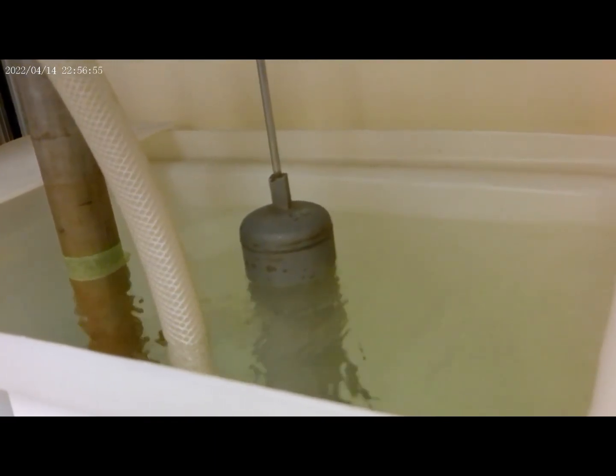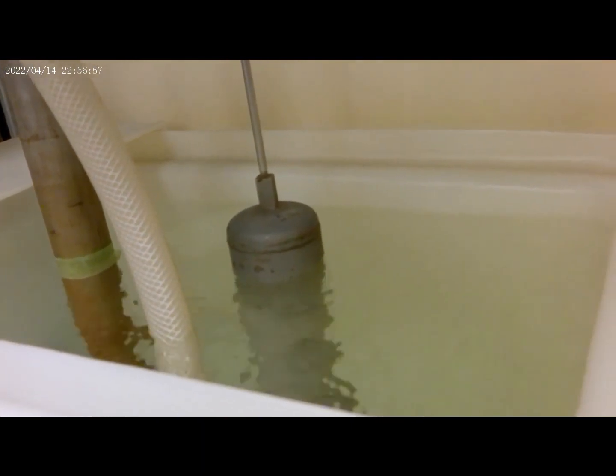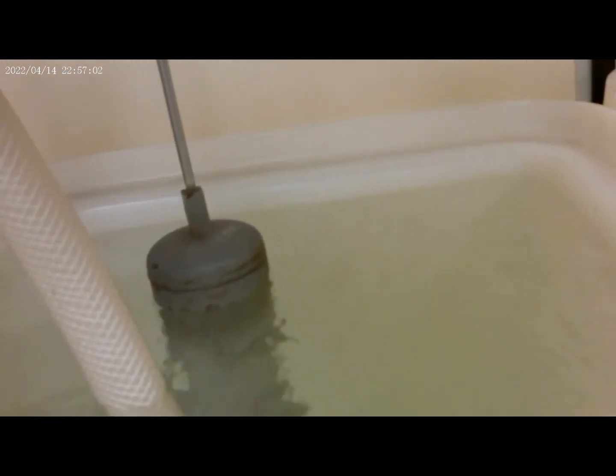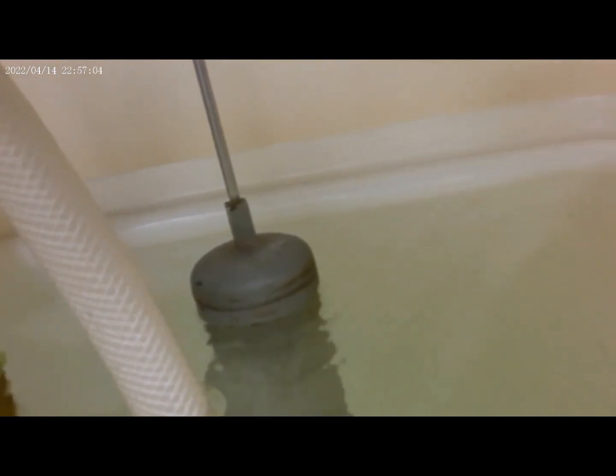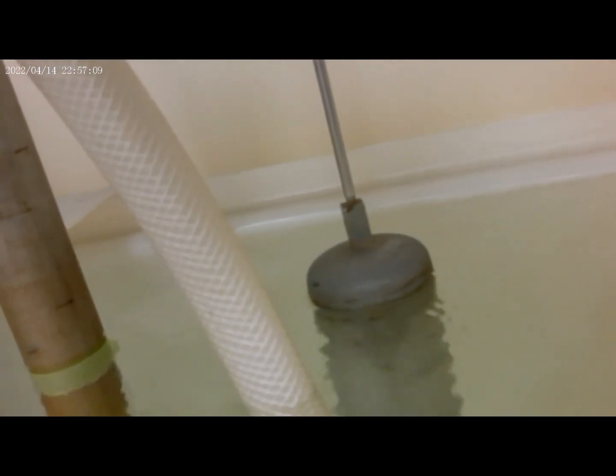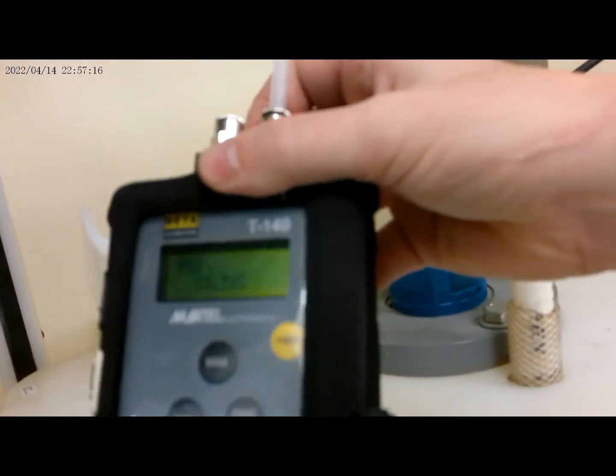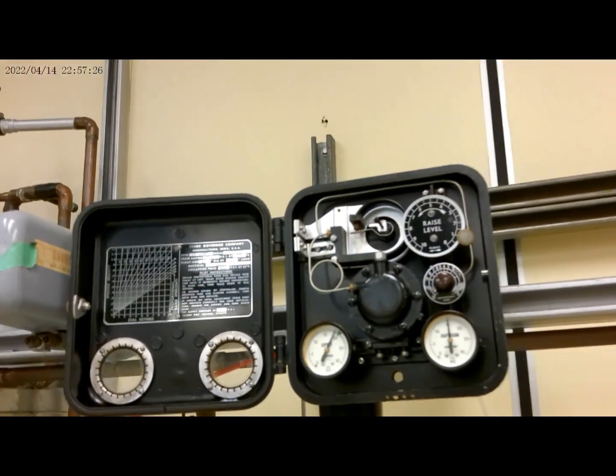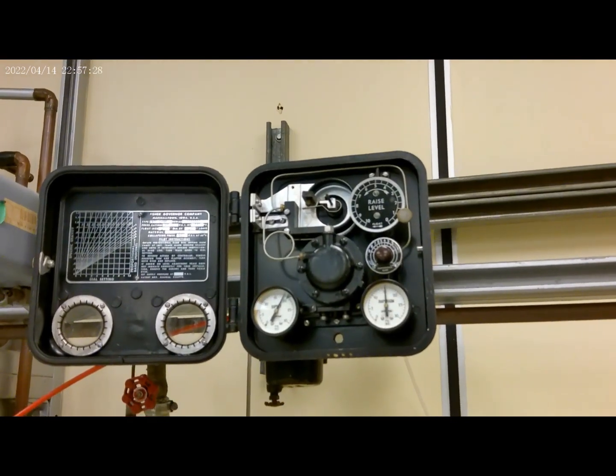We're just coming up to it here, we've got 14 psi, and I have to turn this off. Okay, that's a little over 100%, I went a little too far. So we have 15.3, a little blurry there, and this shows 15 psi output. And so that's the displacer.